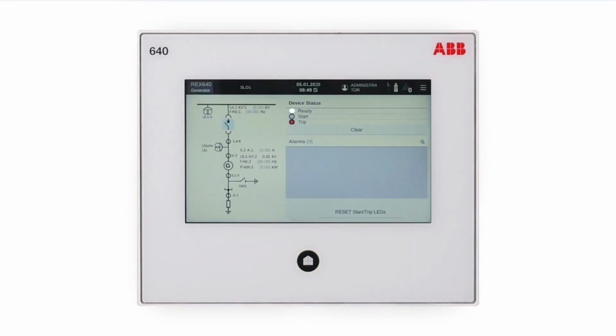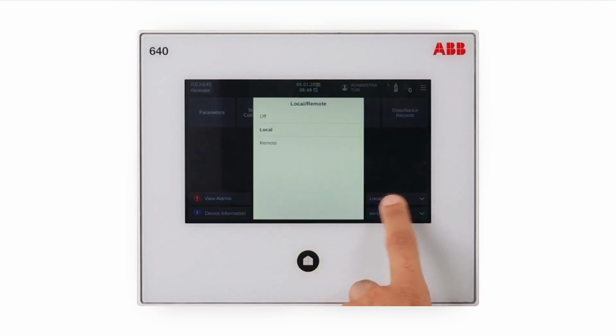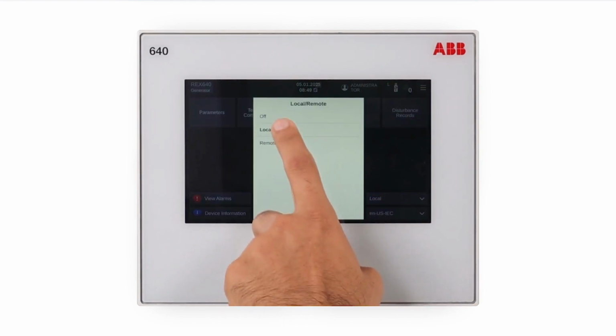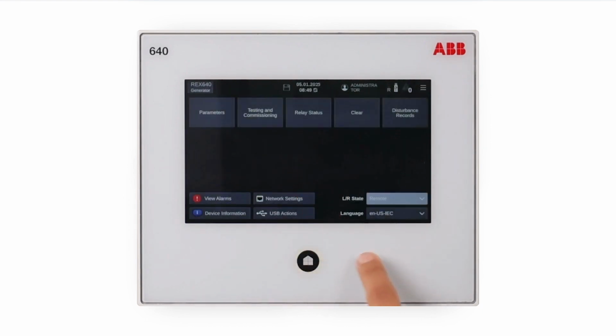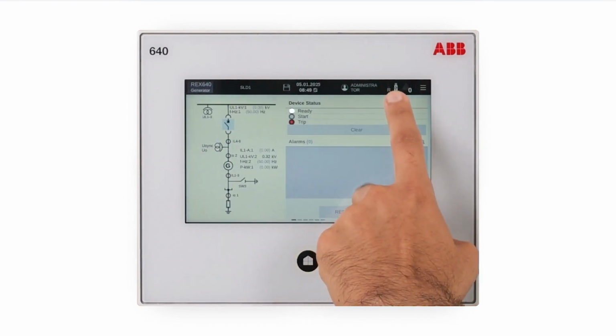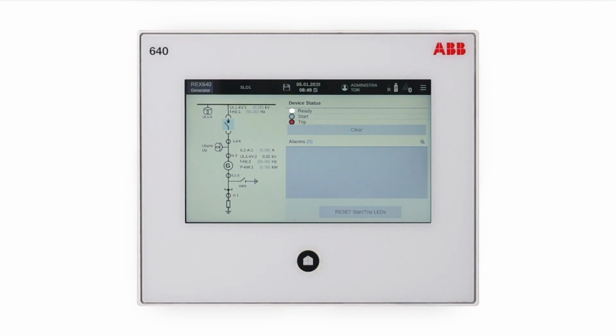Selecting local or remote use. In local position, the primary equipment, such as circuit breakers or disconnectors, can be controlled via the LHMI or SHMI when connected to a selected relay. In remote position, control operations are possible only from a higher level, that is from a control center. The control position of the protection relay can be changed via the local remote dialog box. Tap the menu button. Tap the selection button alongside the LR state text. Select off, local or remote. By setting the station authority parameter, more choices such as L plus R and L plus S plus R will become available.